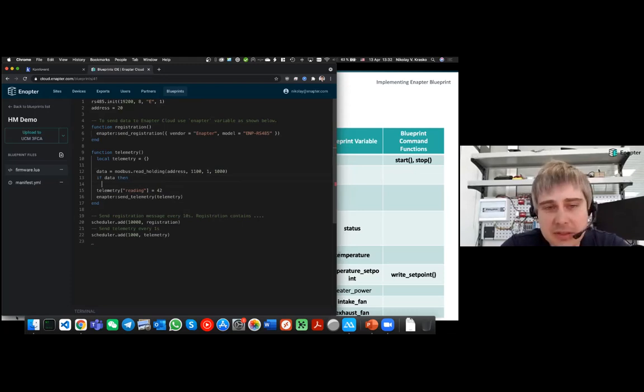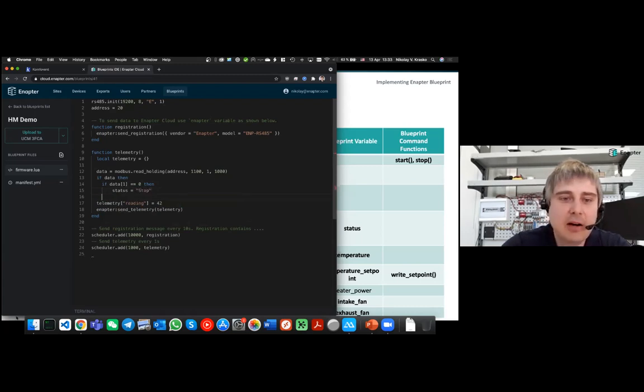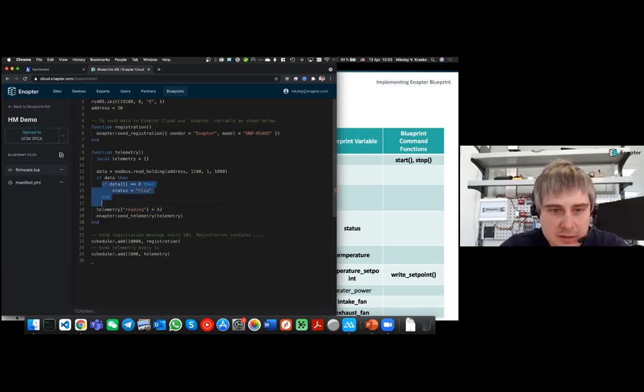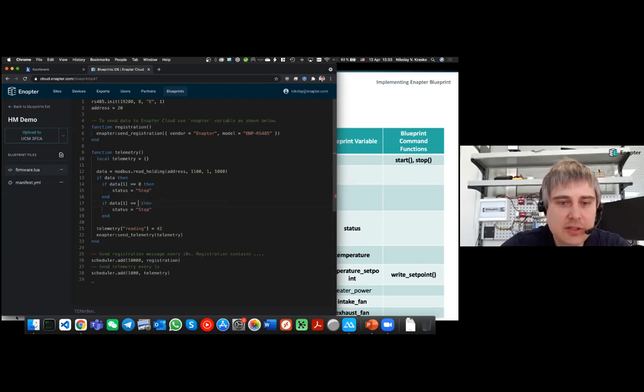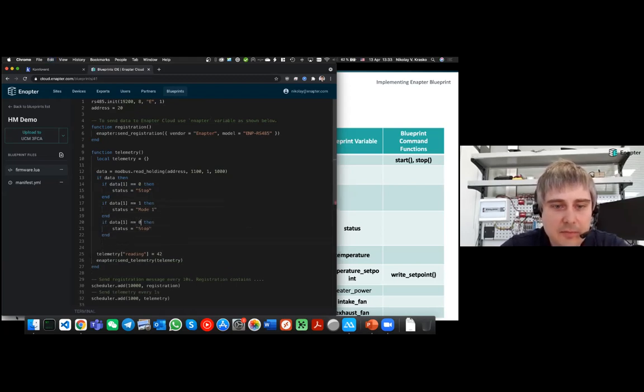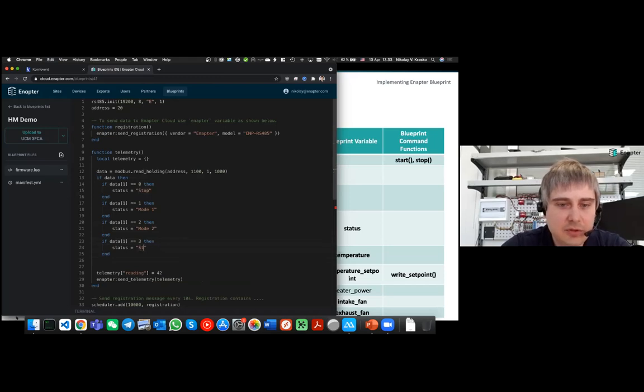Because we have several possibilities for the modes, we need to handle each of these. So if data is equal to 0, then we want to set the status to stop — this means our air handling unit is stopped. The same we need to do with the other modes: if the mode is 1, then it will be mode 1; if it's 2, it will be mode 2; and if data is 3, then it will be mode 3.